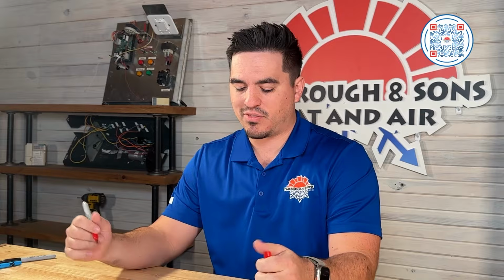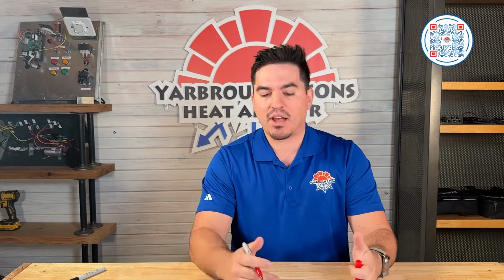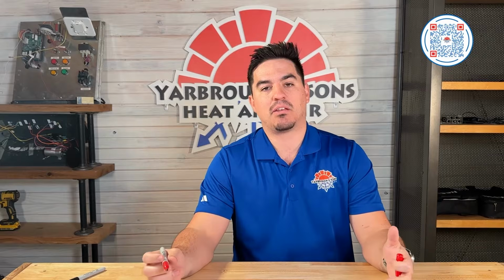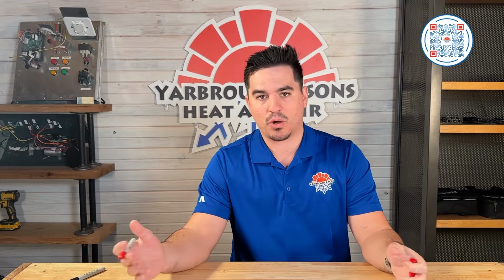Also, whenever a system is sized appropriately, you want to make sure that you have enough return air. And I'm going to give you just a general rule of thumb. A 5-ton system will typically need 3 returns. So 3 returns, sized appropriately. If you've only got 2 returns on that system, I would be concerned.